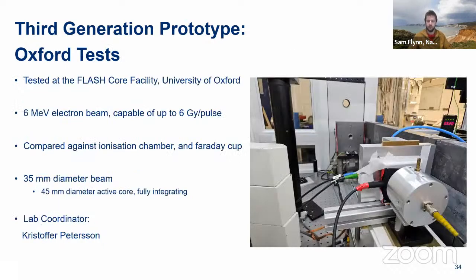So we tested this at the University of Oxford's FLASH core facility. It's an old clinical linear accelerator from the 90s, I believe, that has been repurposed to deliver FLASH beams. They do a lot of studies here for it, and it's a very validated beam. It's clinically relevant, it's 6 MeV, and they've got a robust dosimetry system for doing their experiments there, well, traceable back to us as it happens.